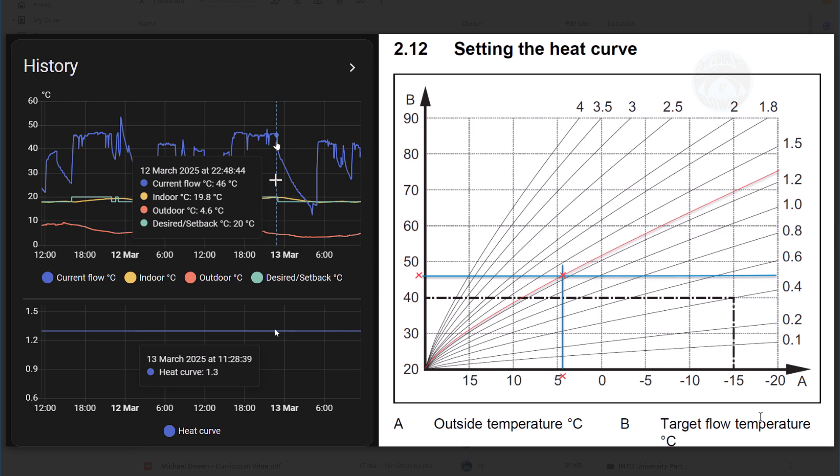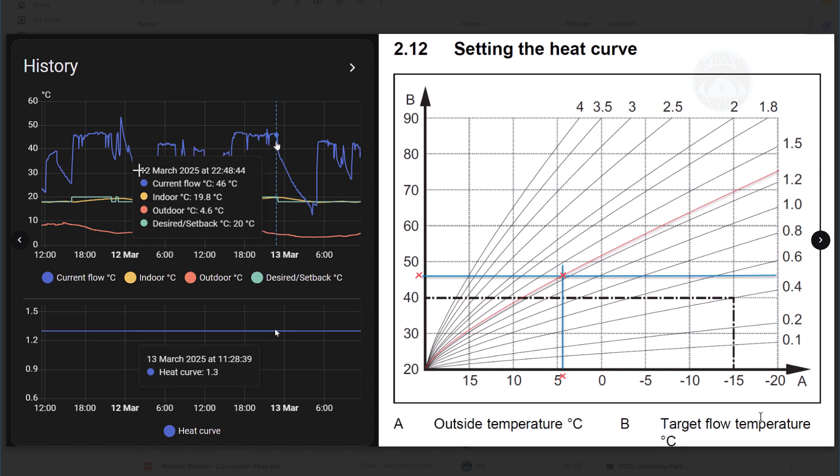And here is an example. 13th of March. It's during the timer period. You can see the yellow line has almost reached the desired temperature. So what I've done is I've put my cursor on my graph. This is Home Assistant, by the way. I can get so much detail out of my boiler data, I should say, out of my boiler to monitor all of this. It's been fantastic. But anyway, if you look at this little square, you can see the current flow temperature is 46 degrees at that time.